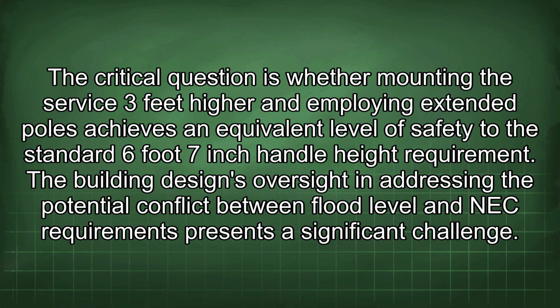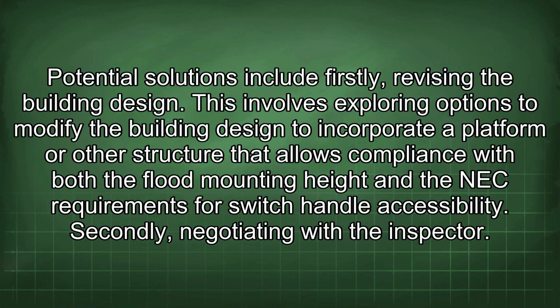The critical question is whether mounting the service 3 feet higher and employing extended poles achieves an equivalent level of safety to the standard 6 foot 7 inch handle height requirement. The building design's oversight in addressing the potential conflict between flood level and NEC requirements presents a significant challenge. Potential solutions include, firstly, revising the building design. This involves exploring options to modify the building design to incorporate a platform or other structure that allows compliance with both the flood mounting height and the NEC requirements for switch handle accessibility.